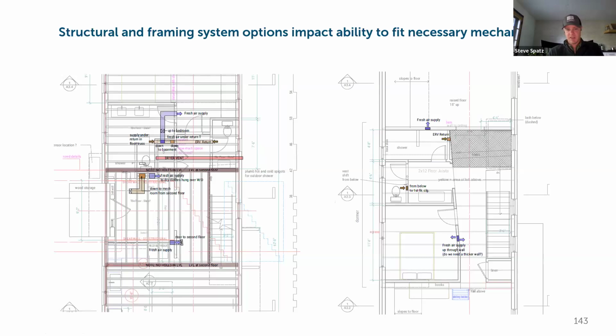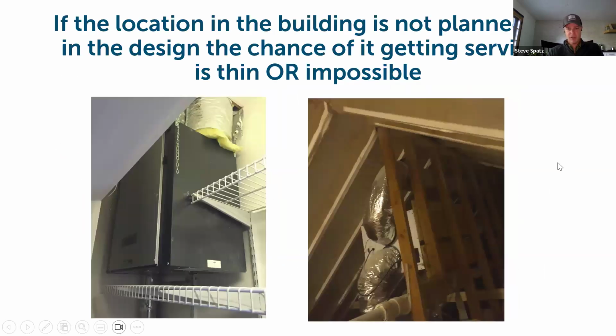You want to be able to get the effective delivered CFMs into the individual rooms in the building. And that comes down to the practical guidelines around duct design, and designing from the room back to the unit, essentially, for how you want to be specifying your terminals, your fittings, your transitions, etc., so that you're getting effective flows from the unit. Because this is an outcome you don't want to see.